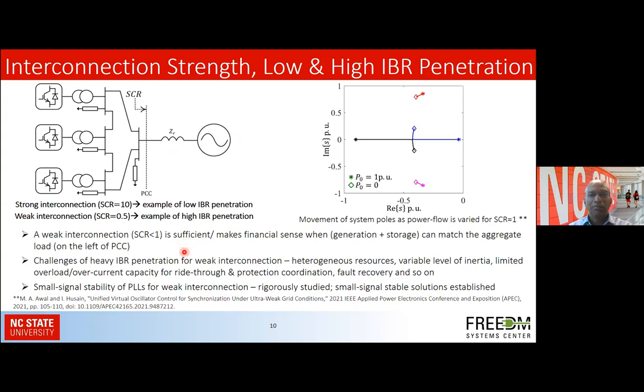It would make sense, if we have enough generation and storage here, to not spend money on strengthening the interconnection here by putting in more transmission capacity, because the local generation and storage should be able to meet the aggregate load demand. Sorry, that was the case when there is a high penetration of IBR, so that would be a weak interconnection, and you don't need to strengthen this grid.